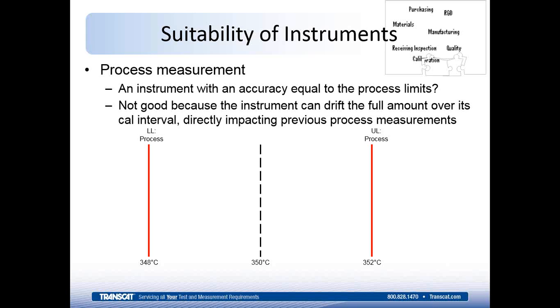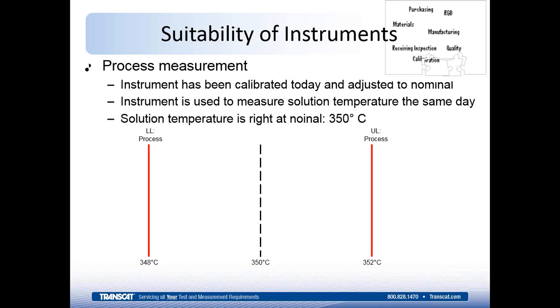All right, so let's say you calibrate the instrument today, and you adjust that instrument to nominal during the calibration, and then it's taken out to be used in this process measurement for the temperature of the solution. So on that same day, you know that the instrument being used to measure that temperature is correct. It doesn't have any error at 350 degrees C. So that process measurement is good, because if I went back and checked that instrument again right after I took the measurement, it's still going to be where it was. Unless I've dropped it or mishandled it somehow, the chances of it varying within that one-day window is very, very minimal. But you don't have the luxury of calibrating your instruments every single day, right?